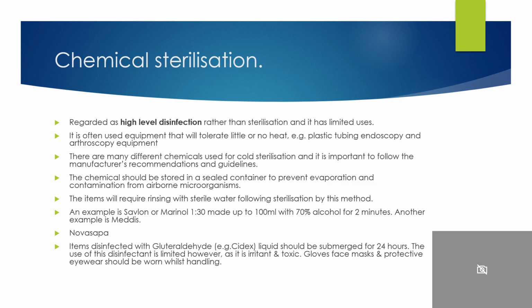Chemical sterilisation. We generally regard it as a high-level form of disinfection rather than sterilisation, and it does have limited uses. It is often used in relation to equipment that will tolerate little or no heat, such as plastic tubing for endoscopy and arthroscopy equipment. There's many different chemicals used for cold sterilisation. It's important to follow the manufacturer's recommendations and guidelines. The chemicals should be stored in a sealed container to prevent evaporation and contamination from airborne microorganisms. The items require rinsing with sterile water following sterilisation by this method.